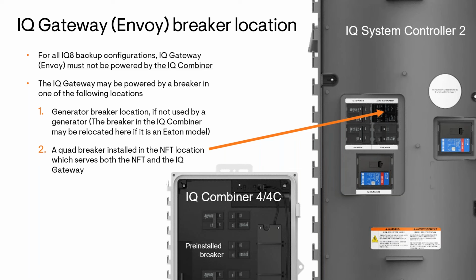Another option is to install an Eaton quad breaker in the upper right-hand location, which is the neutral forming transformer location. Therefore, you would be able to connect both the neutral forming transformer and the IQ gateway to this one quad breaker. And the third option would be the protected loads or backup load sub panel. It can also be installed in there if it just happens to be easier for the installer to put it there. It doesn't make any difference.